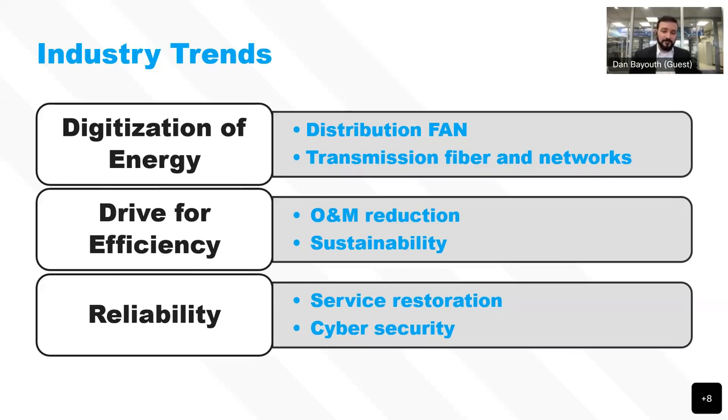Today, SDN in the substation LAN is being discussed actively and is available, where the true benefits of SDN would be an automated deployment based on, say, an IEC 61850 model of the substation. That tells me all of the communications, all those settings files from relays tell me what's talking to what. So I should have a model of what's talking to what that I could compare against the network. And the network should know when anything outside of those defined devices is trying to talk on the LAN. So from a security and segmentation standpoint, all of these come together. And it'd be nice if I just throw my files in the controller and everything's provisioned.